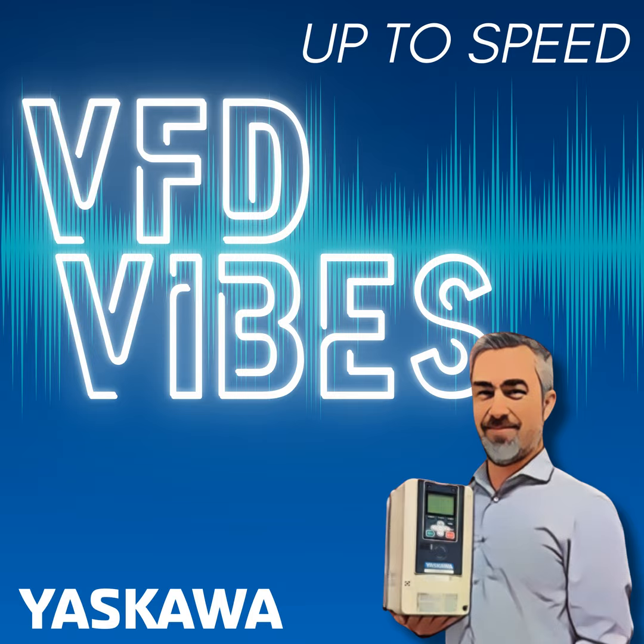But one of the things I always had them do was change their accel and decel times, especially if it was a fan, from 30 seconds, which is our default setting, to something of 60 seconds or larger. If it was a 100 horsepower fan, I might have them turn it up to 90 seconds or something longer than that. And that would be C, like Charlie, 101 for our accel, and C102 for our decel times.